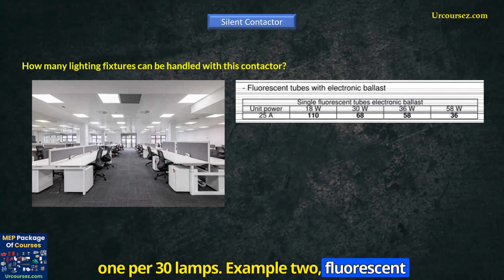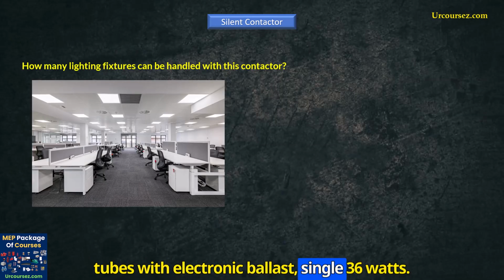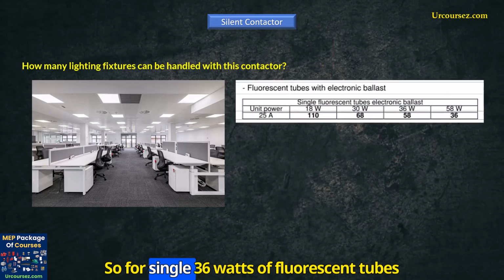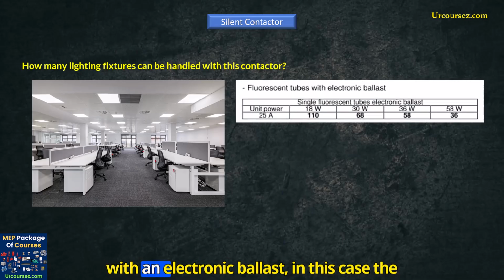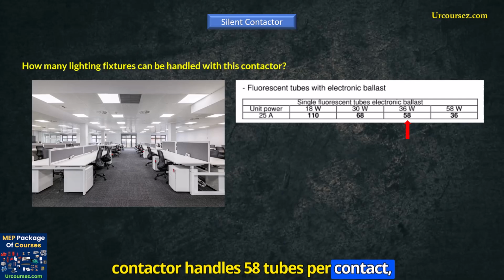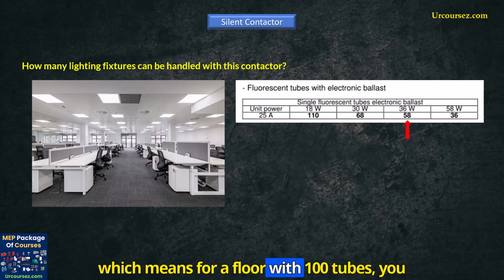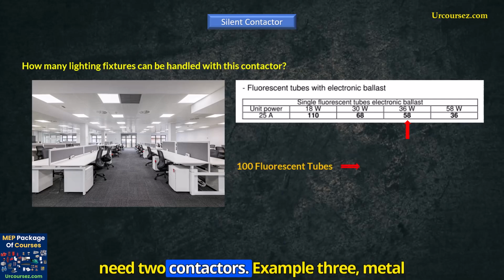Example 2, fluorescent tubes with electronic ballast, single, 36 watts. So for single 36 watts of fluorescent tubes with an electronic ballast, in this case the contactor handles 58 tubes per contact, which means for a floor with 100 tubes, you need 2 contactors.